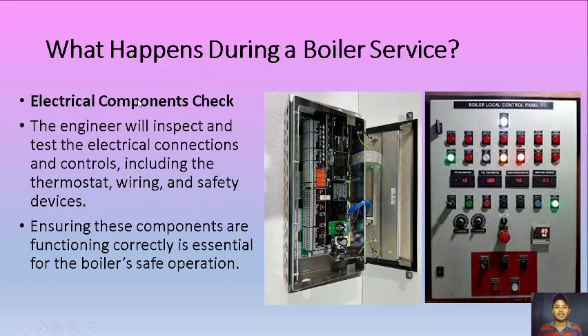Okay, next we have the electrical components check. Inside this control panel, we have so many electrical components that we have to check. Usually, we check for loose wirings. We check if the contactors are moving, and we also test the emergency stop to see if it's working. The engineer will inspect and test the electrical connections and controls, including the thermostat, wiring, and safety devices. Ensuring these components are functioning correctly is essential for the boiler's safe operation, especially the emergency stop. You should test if it's working.